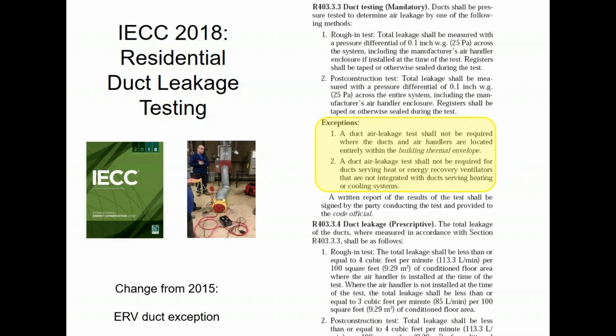If your furnace or air handler is installed, you get 4 instead of 3 because they know the air handler is going to leak a little bit. Honestly, most furnaces and air handlers leak a little bit more than 1, so you're better off on a new install doing the duct testing prior to putting the air handler in. But in any case, you get 3 or 4 CFM for every 100 square feet of home. So if you had a 2,000 square foot home, that would give you 20 times 4. You'd have a maximum of 80 CFM of leakage if your air handler was installed, and 60 CFM if you're multiplying by 3 instead of 4, if your air handler wasn't installed.